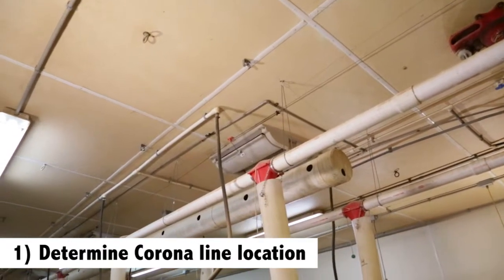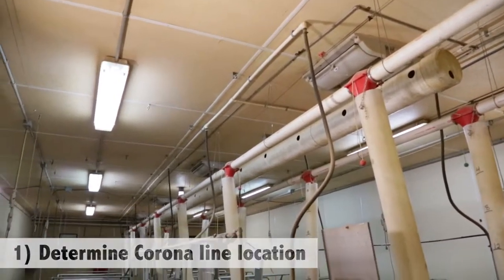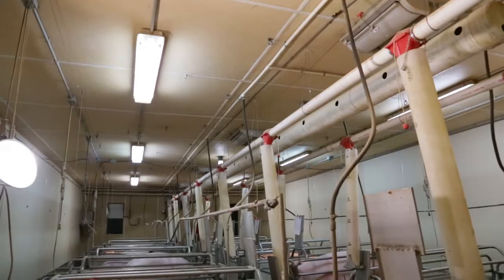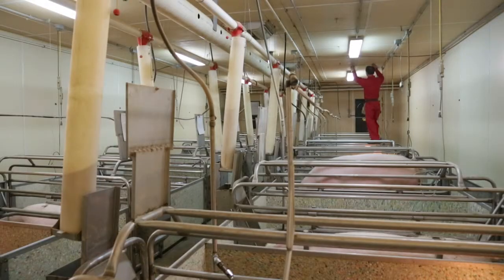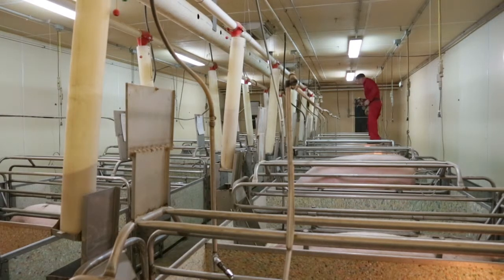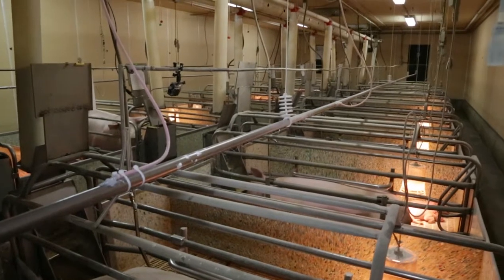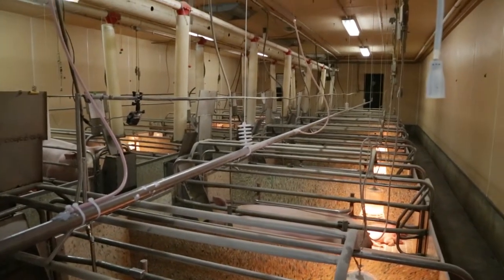First, determine where to install the corona pipe lines. A corona line ideally energizes a 10 foot wide lane which is typically centered over 10 feet of pen space. Determine the best location to install corona pipe drop line supports. Evenly center the corona pipe over the pig space. During operation, the corona pipe must be at least 6 inches away from any objects.